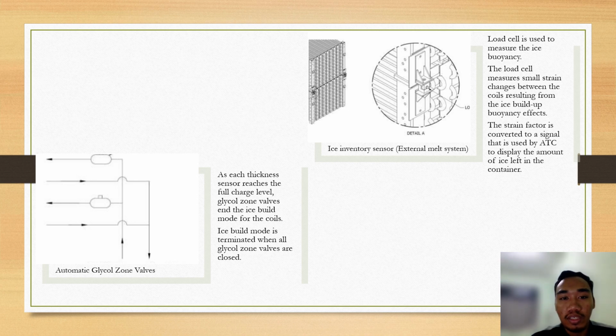The next part is the ice inventory sensor for the external melt system. A load cell is used to measure the ice buoyancy. The load cell measures small strain changes between the coils resulting from the ice build-up buoyancy effect. The strain factor is then converted to a signal that is used by automatic temperature control to display the amount of ice left in the container.